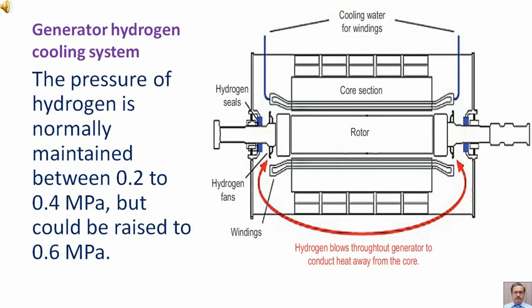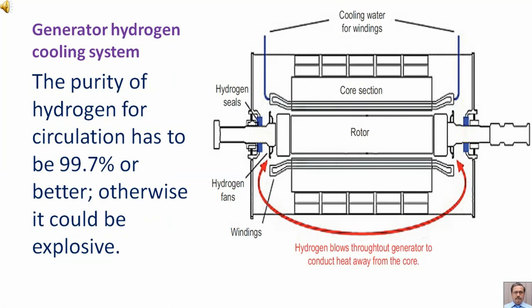The pressure of hydrogen is normally maintained between 0.2 to 0.4 MPa but could be raised to 0.6 MPa. The purity of hydrogen for circulation has to be 99.7% or better. Otherwise, it could be explosive.